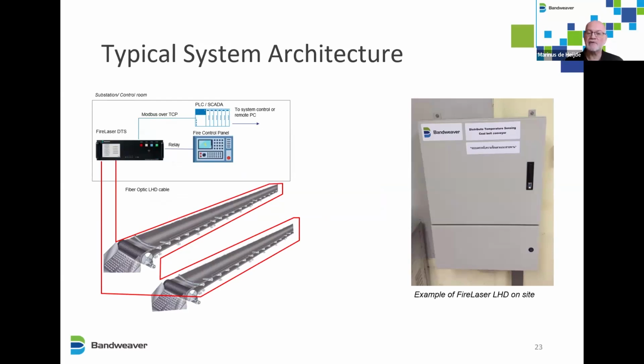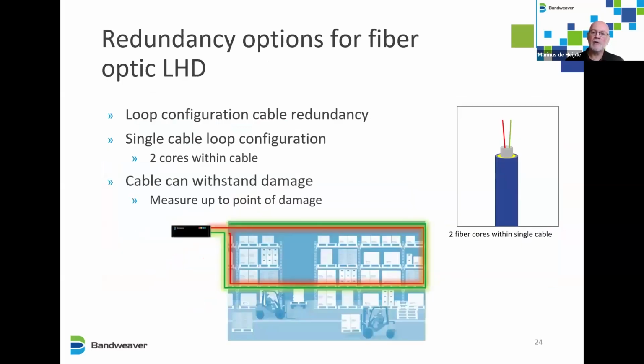But we can also connect via Modbus over TCP to a PLC, SCADA, or BMS, building management system, to give more precise information. What we see here is a loop configuration. The unit would be a 2-channel unit, so the cable comes out of channel 1 and goes back into channel 2, making it a redundant system, which we'll cover in the next slide. So, a loop configuration, cable redundancy with a single cable. Every cable has 2 fiber cores, so you get 2 for the price of 1, you could say. If there is damage to the cable, there is still a fully functioning system.